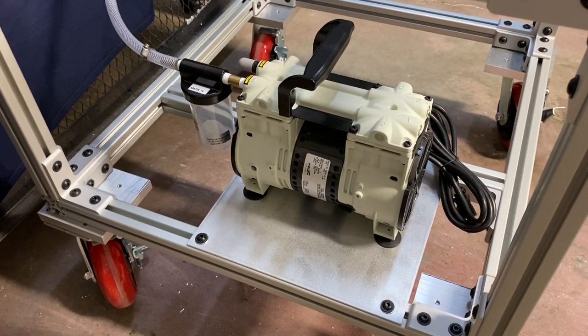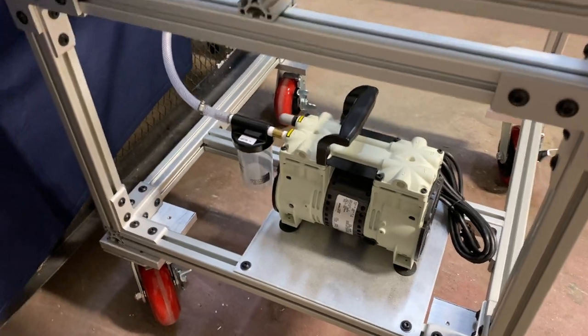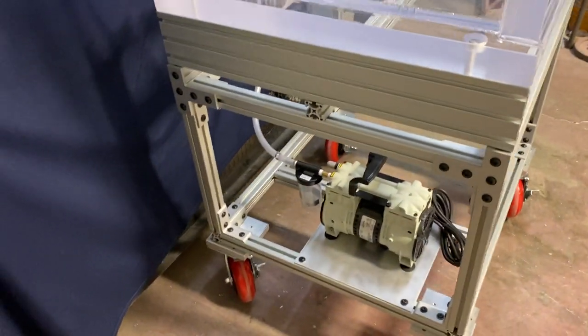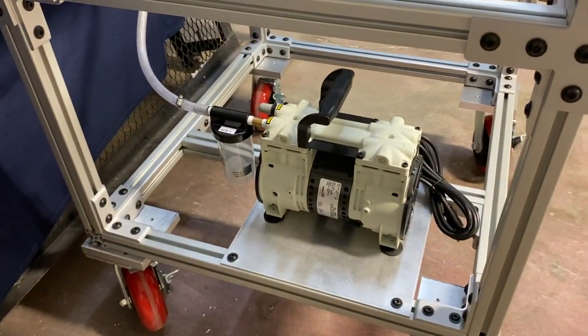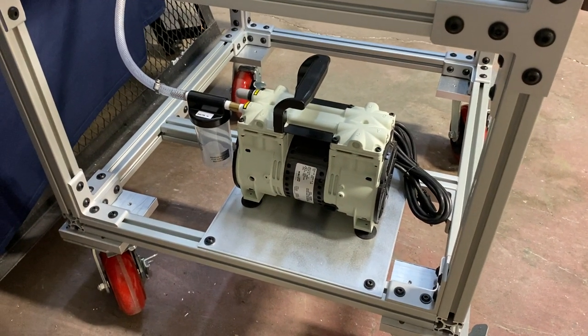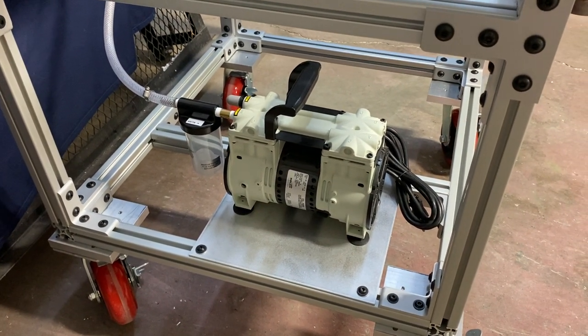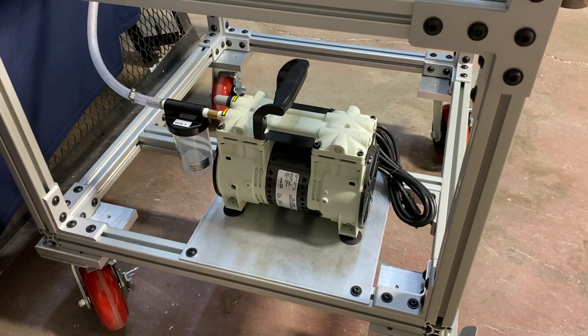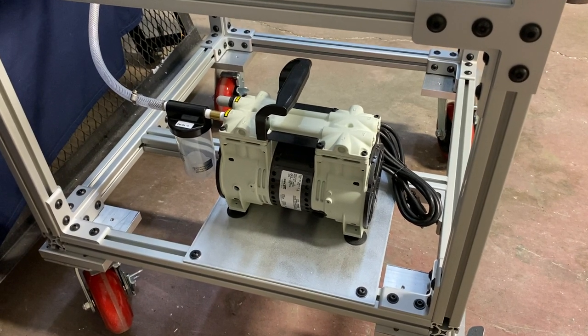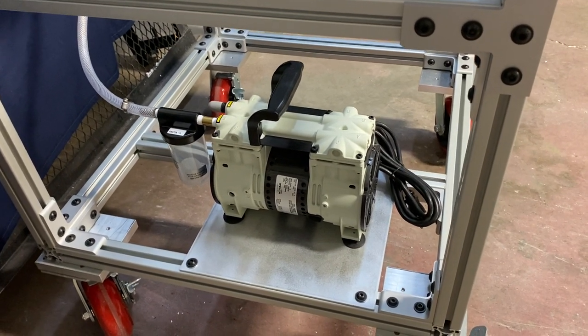and of course the advantage of that is that this vacuum pump does not require any maintenance and you don't need any oil to run it and the cost is that it doesn't pull as high of a vacuum. However in vacuum bubble leak testing you do not need to pull a high vacuum.